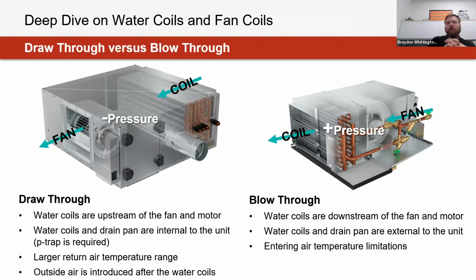Whereas once we start to get into blower coil territory, that's when you get into that 1 inch to upwards of 4 inches of total static, which is what that blower coil is really trying to compensate for. You'll see with some of the renderings as well, all of these have some form of drain pan for the condensate management system, just because the likelihood is that there is going to be some condensation happening at the coil itself.